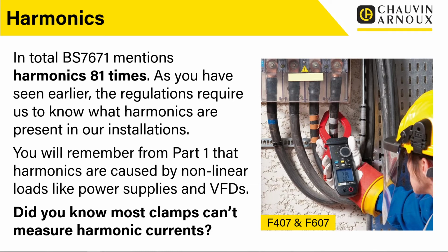So this is true. Most clamp meters that you will come across, most normal clamp meters, are often filtered just for the 50 hertz, 60 hertz that they're likely to be measuring. So they don't pick up the frequency bandwidth either side of that. They don't pick up the harmonics. So in a lot of cases, you could be using your clamp meter, thinking you're measuring the current, but it's not the true current. It's just the current at the fundamental. It's not the current across the whole harmonic spectrum. So if you've got harmonics in there, you're not going to be picking that up unless you use a clamp meter that is specifically designed to do that.